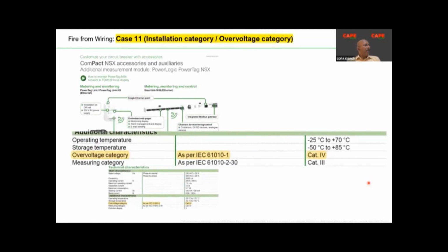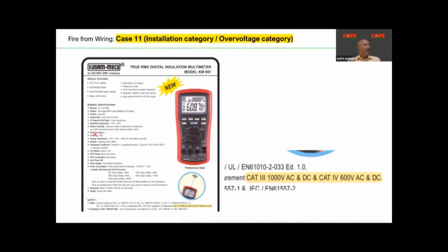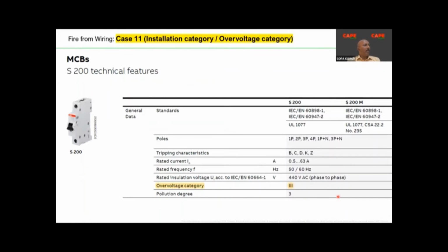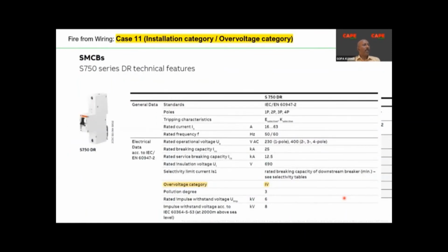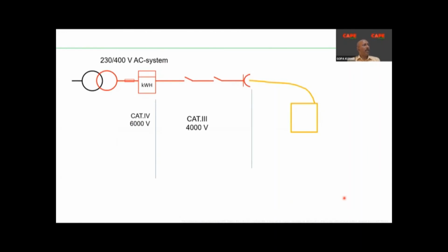Number 11, over voltage category or installation category. I'm just showing you some of the catalogs of some of the products. For example, for an MCCB, you can see a parameter in their catalog, over voltage category, Cat 4. Multimeter, Cat 3, 1000 volt, Cat 4, 600 volt. MCB, over voltage category 3, another MCB, over voltage category 4. What it means is, in your electrical installation, you must select and install electrical apparatus appropriately in such a way that at the origin of installation, that means at your main switchboard, category 4 devices are used. At the distribution, category 3 devices are used.